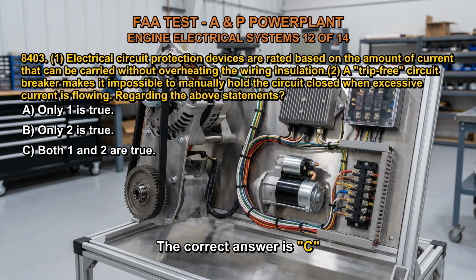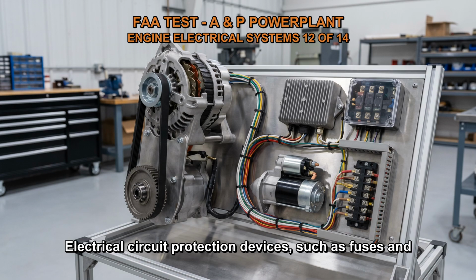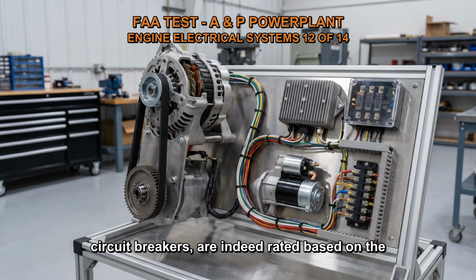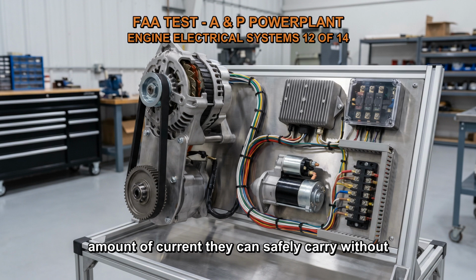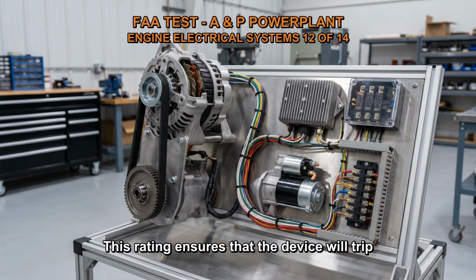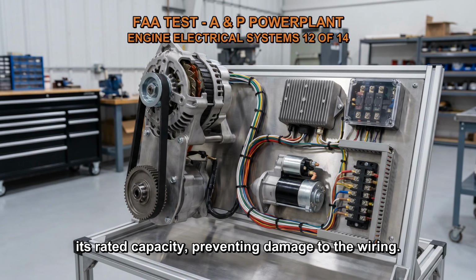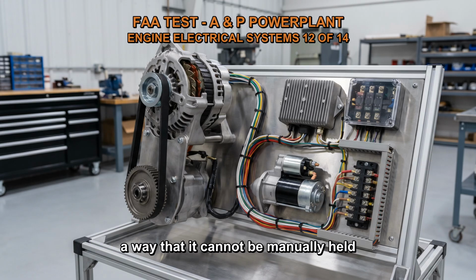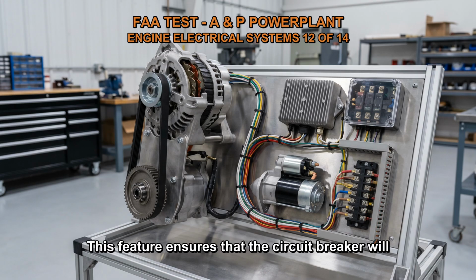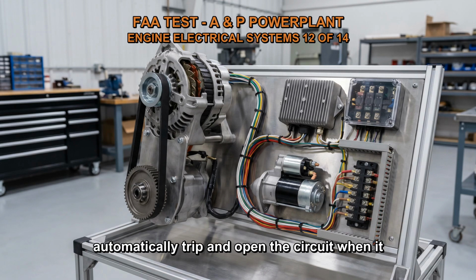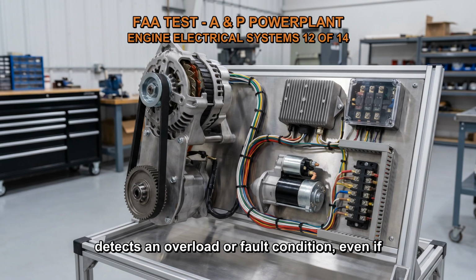The correct answer is C. Electrical circuit protection devices, such as fuses and circuit breakers, are indeed rated based on the amount of current they can safely carry without causing overheating of the wiring insulation. This rating ensures that the device will trip or open the circuit when the current exceeds its rated capacity, preventing damage to the wiring. A trip-free circuit breaker is designed in such a way that it cannot be manually held in the closed position when excessive current is flowing through the circuit. This feature ensures that the circuit breaker will automatically trip and open the circuit when it detects an overload or fault condition, even if someone attempts to hold it closed.